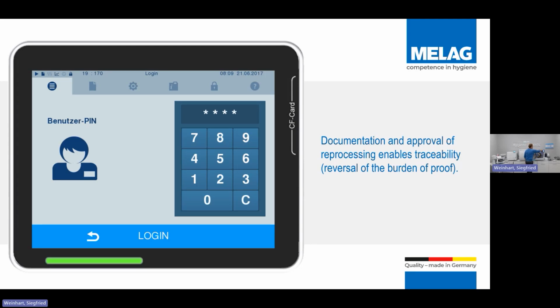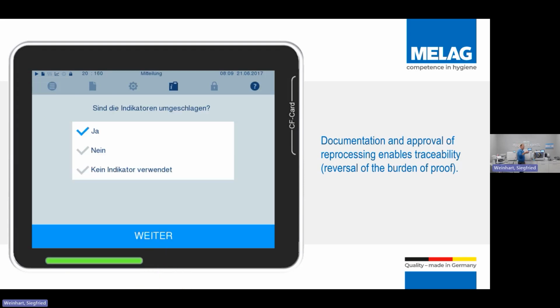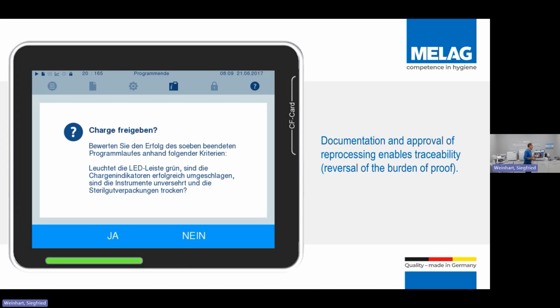And then when it finishes, it pops up on the screen that the user has to put in their little 4-digit code. So they will log in. It will then ask them, has the indicator, i.e. the little test strip that you either put onto the pouches or you put on the helix, changed color? Okay, yes or no? If it changed color, you would tick yes. It's then asking you, were there any error codes on the unit? Did the little warning bar come up with an error on there, to ensure it didn't pick up any issues? If it was all fine and it said on the screen, cycle completed successfully, then you'll tick yes.